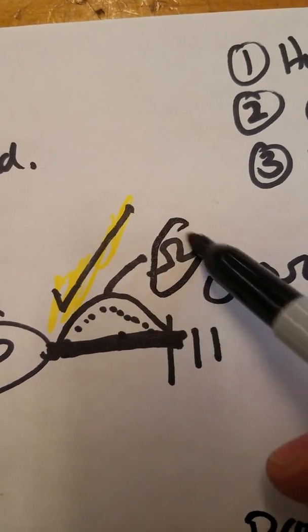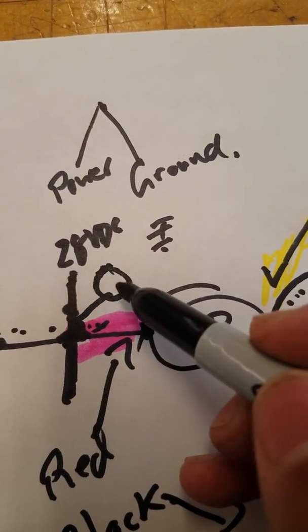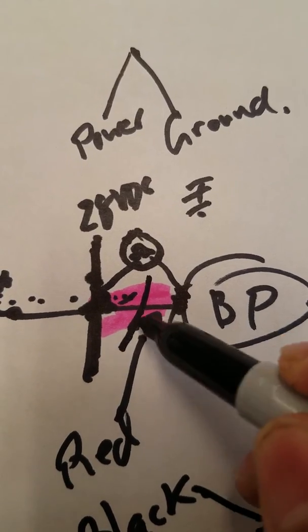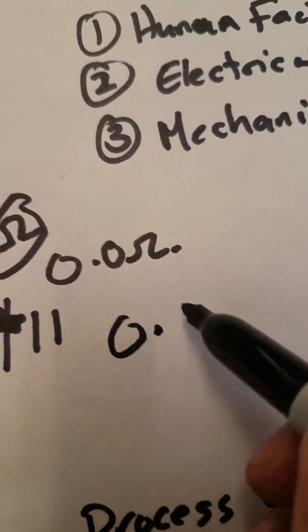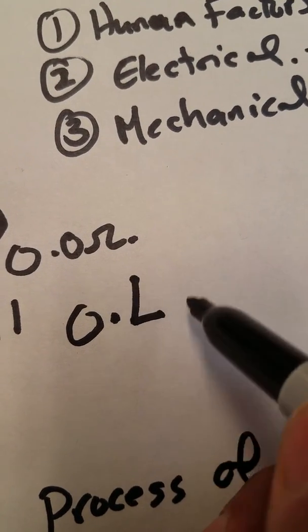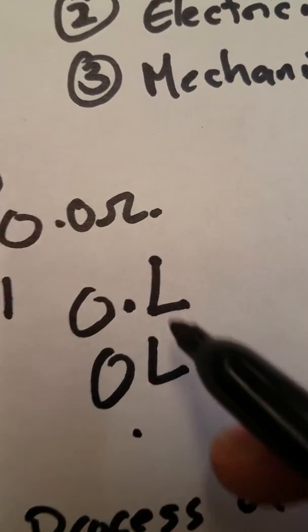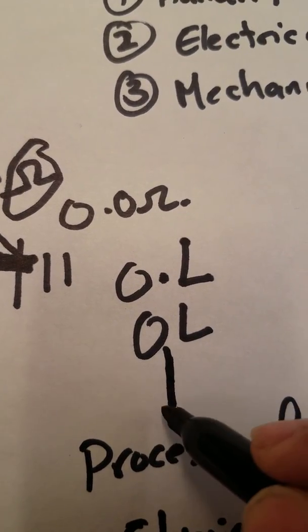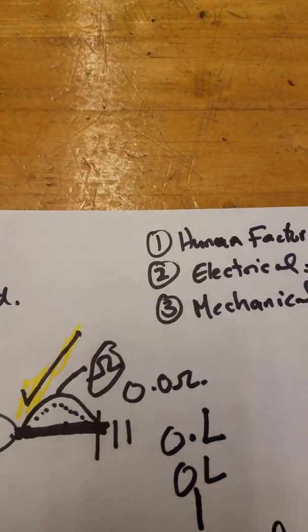To confirm, do a resistance check from the terminal strip to the boost pump connection. Place the meter leads between those two locations and check for resistance. If the wire is good it should read close to 0.0 ohms. But in this case, more than likely there is a break in the wire, so it will not read 0.00 — it will show an open load, or the meter will just display a '1' and not move. If you see open load or a '1,' that means there is an open in the wire, and you've found your problem — it is electrical.